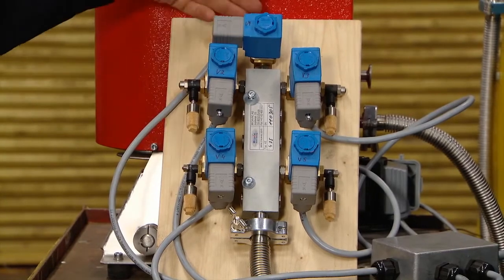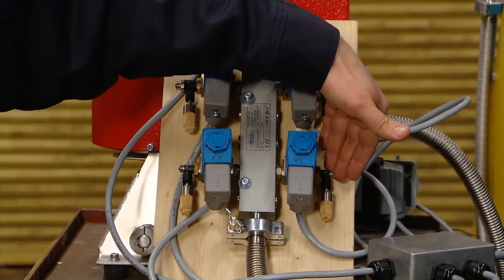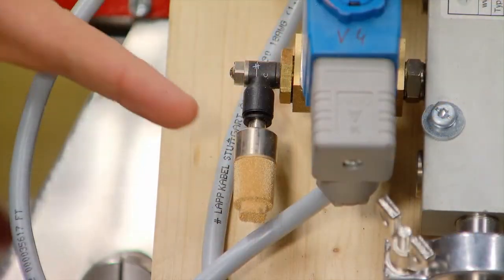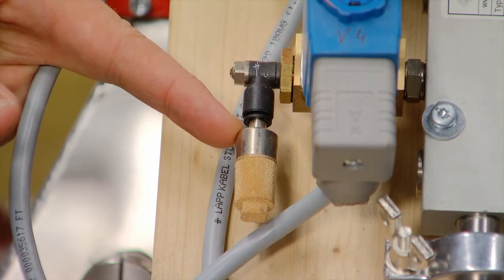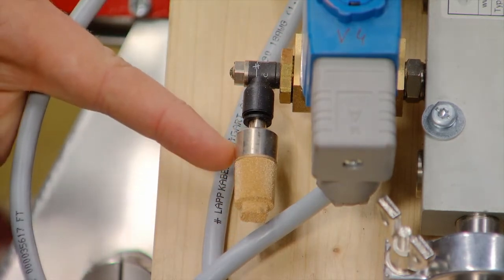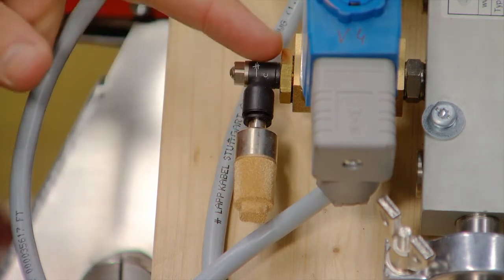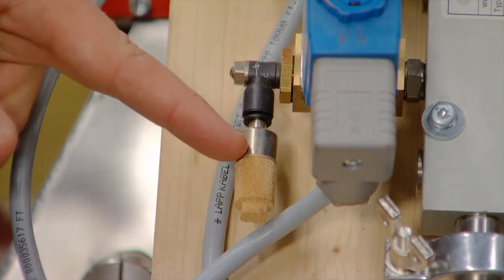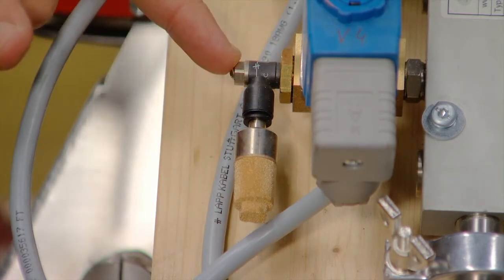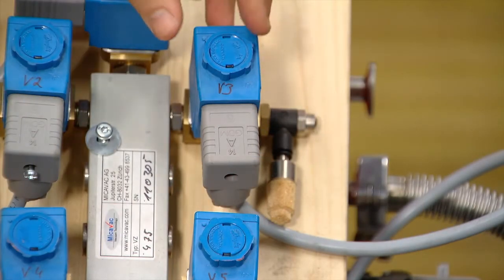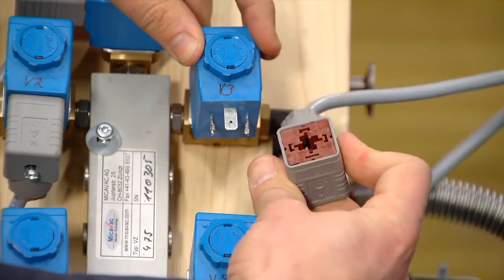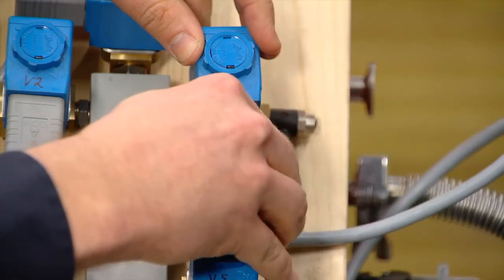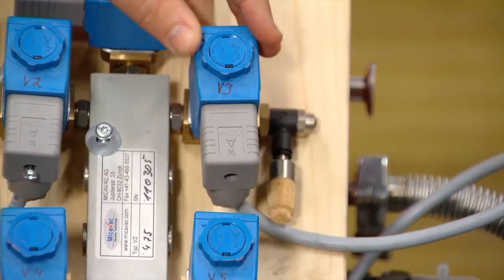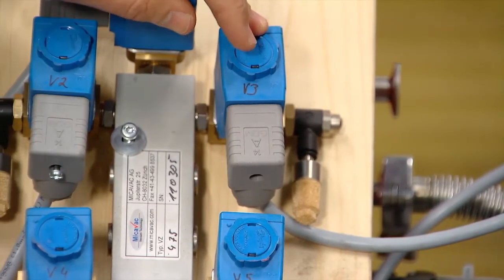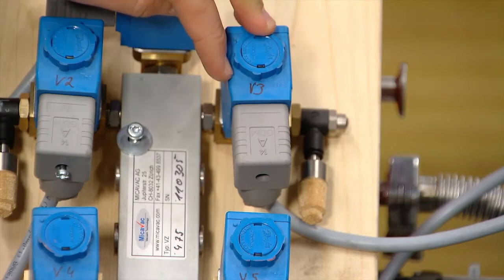The second, third, fourth and fifth valve can be seen. This is the calibrated part of the valve with the silencer, which is generating the calibrated leakage rate. This black here is a plastic part which connects the silencer to the magnetic valve, and that's where you have the sensitivity. Handle with care. When mounting and dismounting the valves, disconnect the caps from the valves and reconnect them again. Make sure each valve has its corresponding cap. Valve 3 in this case has cap number 3.